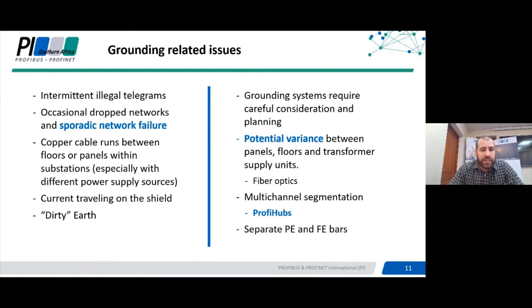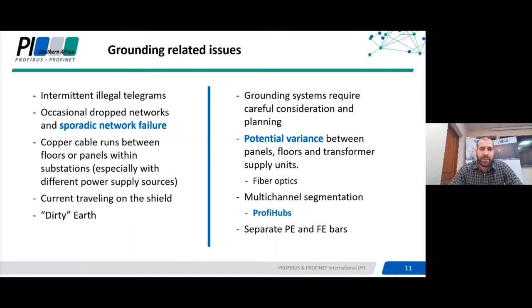Another fix found extremely useful where you have grounding related issues, rather than an expensive redesign of the whole grounding system, is in some cases you can use multi-channel segmentation using something like a Profibus hub, which has multiple channels and allows you to create a star topology. This makes devices on the network a lot more immune to these types of interferences. Obviously also utilize separate protective earth and functional earth bars.